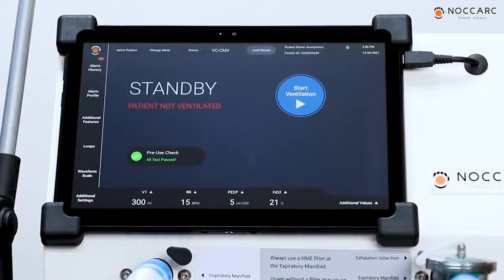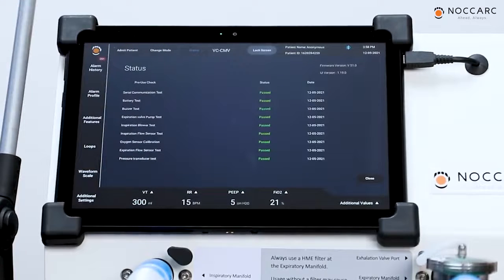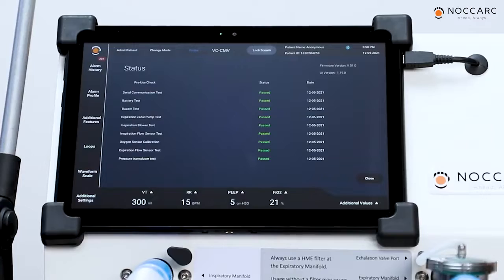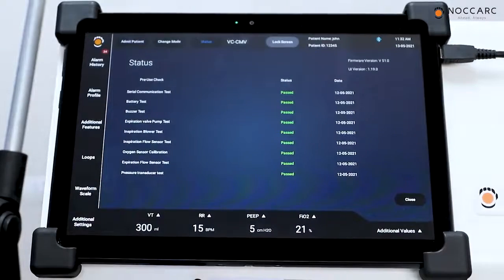The status of the last pre-use check is shown in the standby screen, in the status option in the top bar. Here you can see all the tests displayed, the status of each test and the date on which we performed the pre-use check. If any of these tests fails during pre-use check, in that condition the ventilator will not be started. In that condition, you have to contact an authorized service provider for troubleshooting and servicing of the ventilator for normal operation.